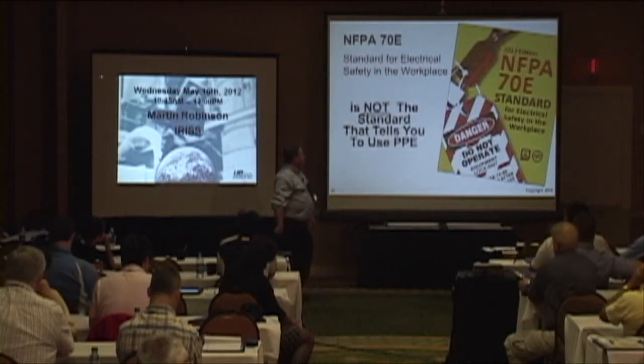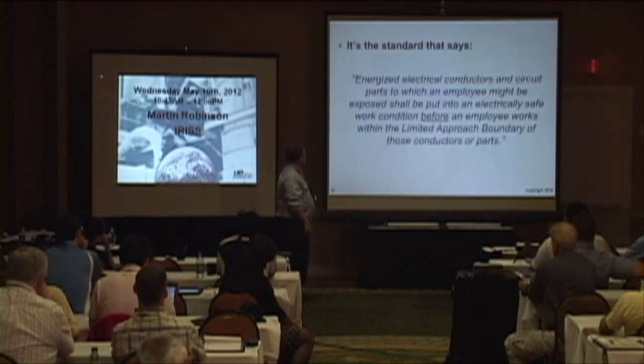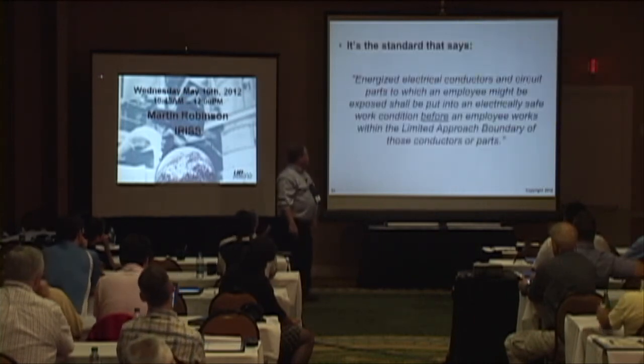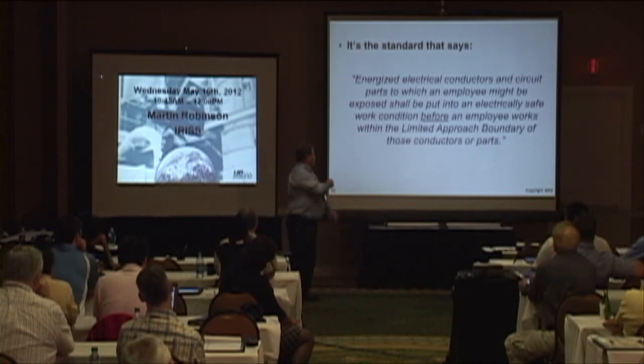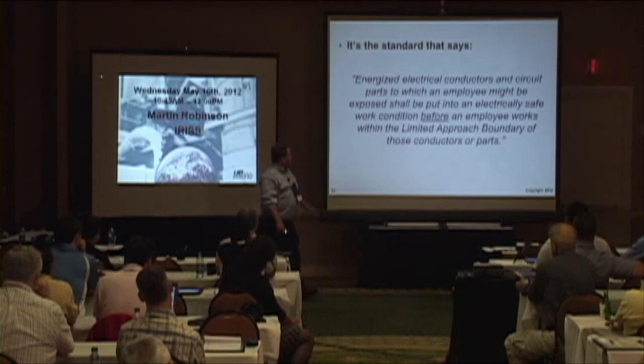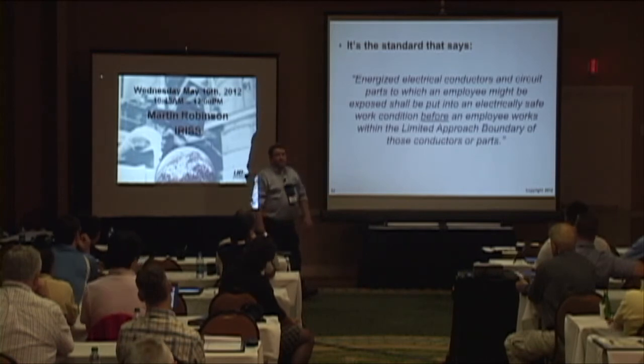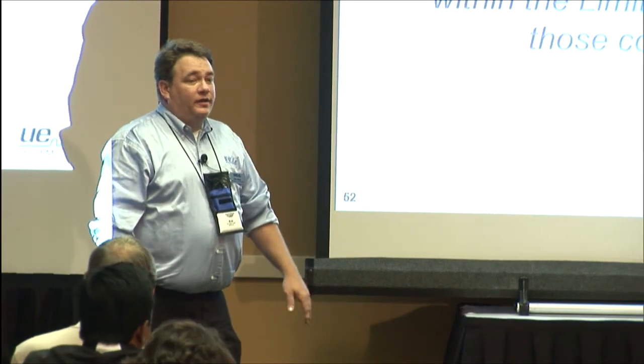70E is really not the standard that tells you to use PPE. It says, energized electrical conductors and circuit parts to which an employee might be exposed should be put in an electrically safe work condition before an employee works within the limited approach boundary of these conductors or parts. It's not about PPE. It's all in there.